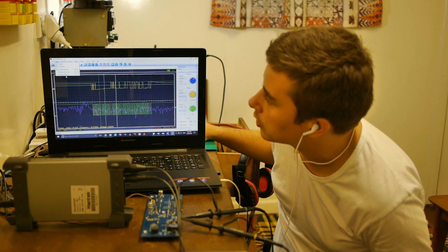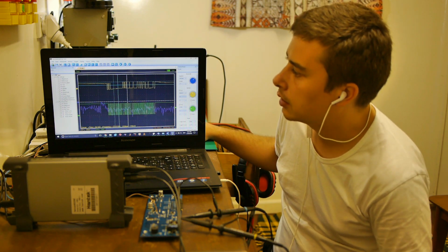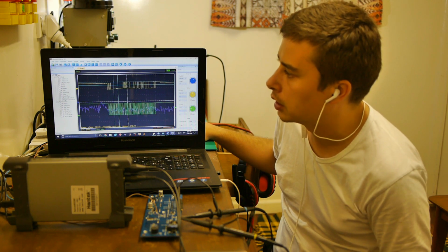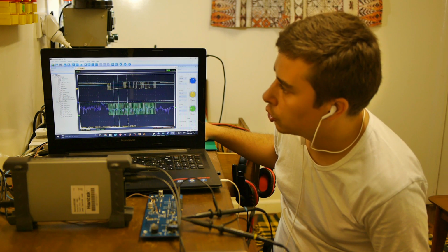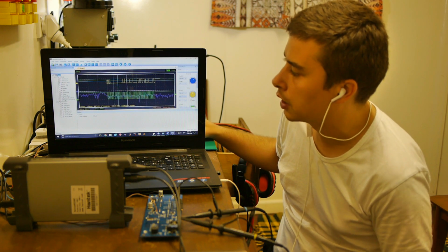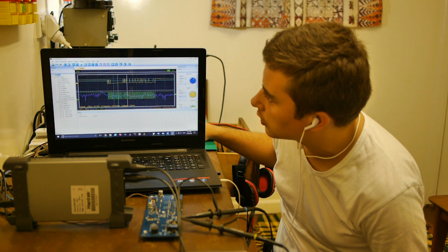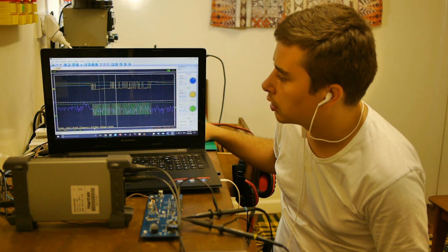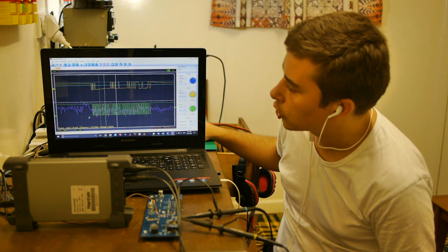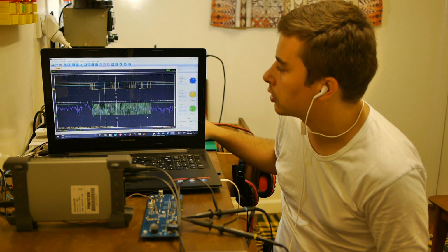There is a separate menu which is called Measure Window, and when you access it, it displays a left side menu here, and you can select some measurements that you can put on the screen. So you can have the minimum, maximum, peak to peak value, and when you select that respective measurement, then you will see the value displayed in the chart here on the screen, and that's a very important thing to have. Anyways, for measuring the frequency, the period, the time, and the amplitude, you have these automatic measurements here on the screen. You don't have to do anything else but to set some cursors here on the screen.